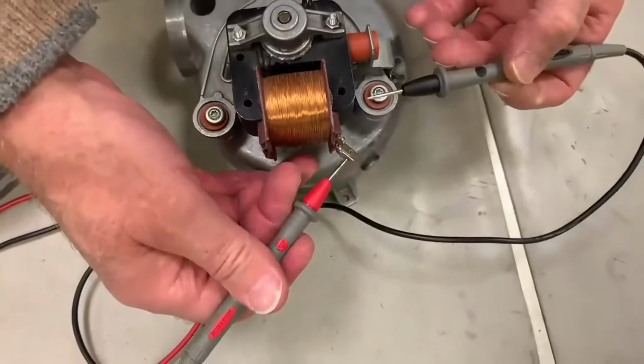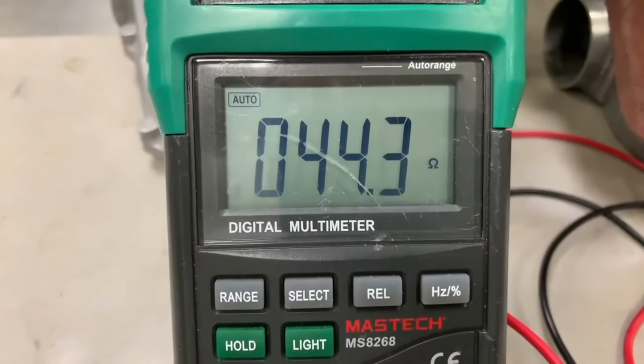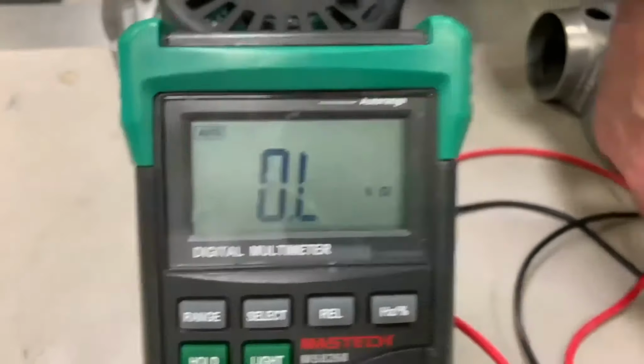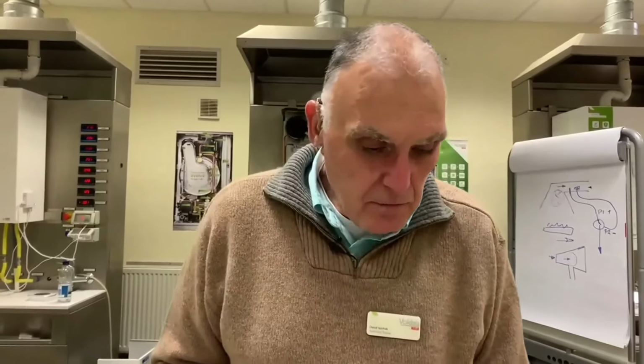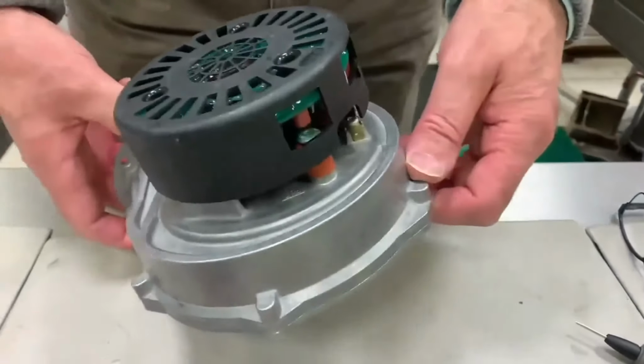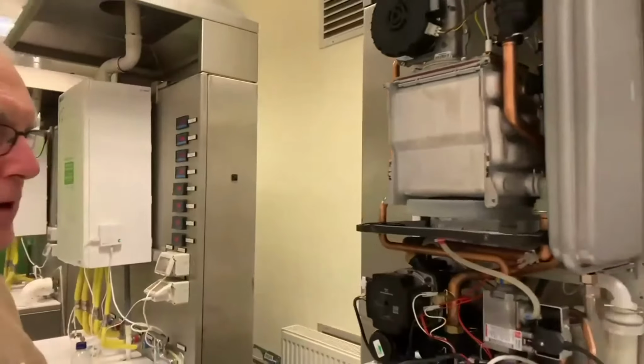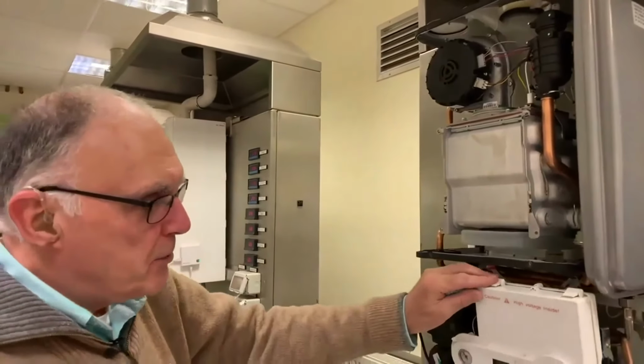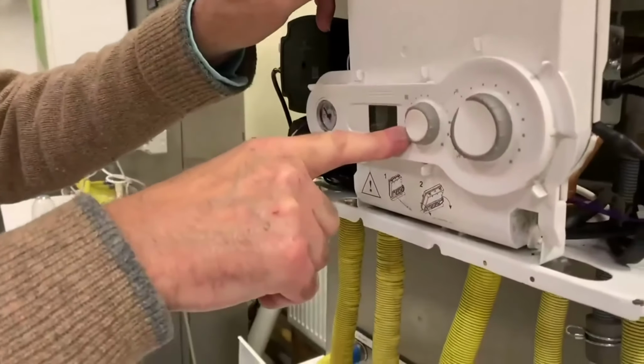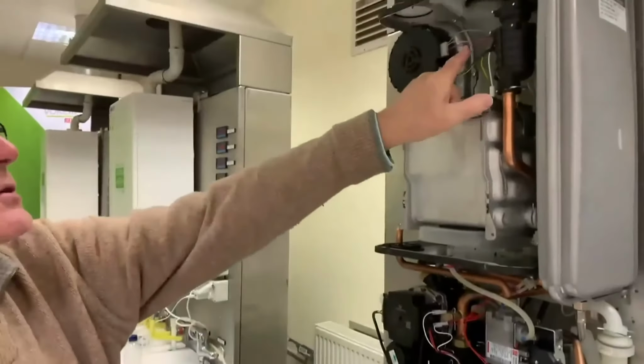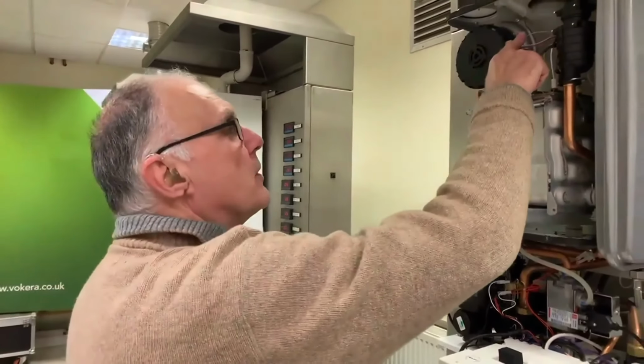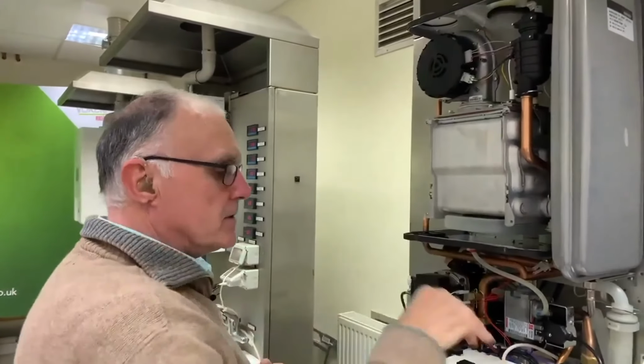So if we put a probe on here, this has got a resistance of 44 ohms. Most of ours will fall between 19 and 70 ohms. All of the fans will have a resistance that you can relate to. They're the easy ones. The more tricky one is the latest style of fan, and this has two connections. I was told the easy way to check whether it's the fan or the board: put the boiler into standby, so there's no demand. And we've got two sets of connections. Pull the control wires out because they're low voltage. If the fan turns, it's the board.